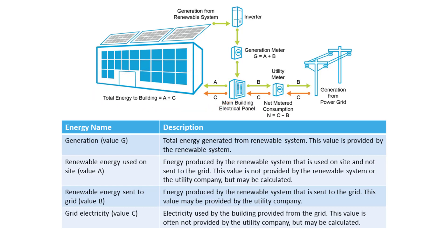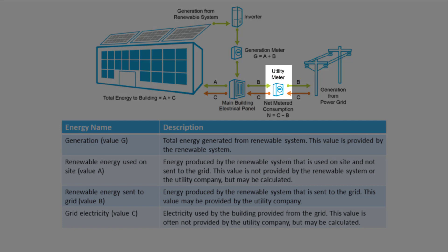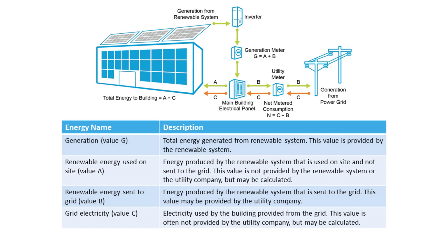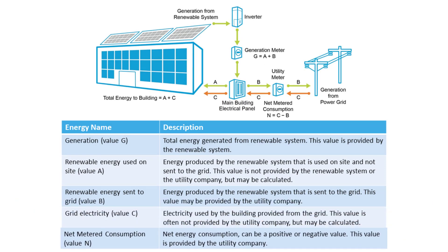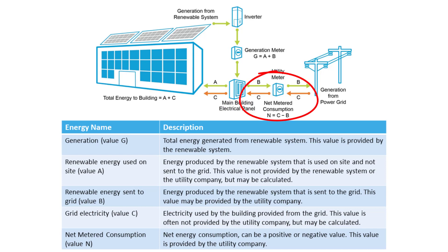Excess electricity generation sent back to the grid, or Flow B, is measured by the utility meter before leaving the premises. However, many utilities do not provide this value on the utility bill that goes to the customer. In such cases, the utility only provides customers with the net metered consumption, or N, which is equivalent to Flow C, grid electricity, minus Flow B, energy generated on-site and exported to the grid.